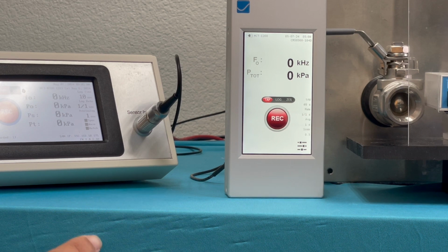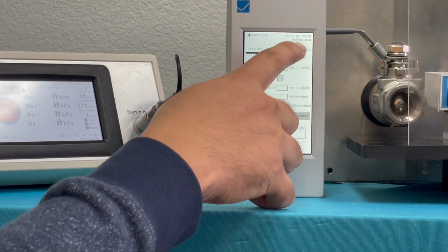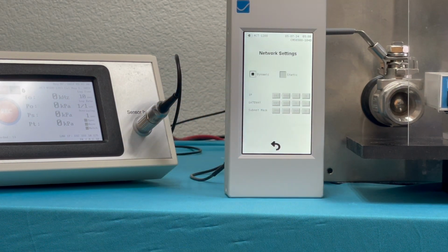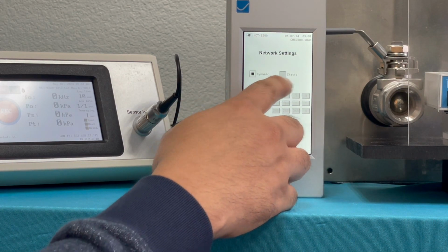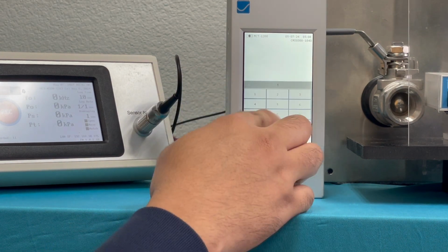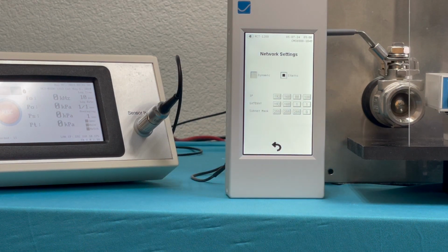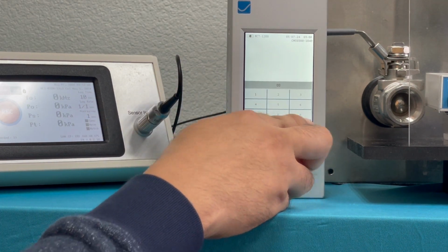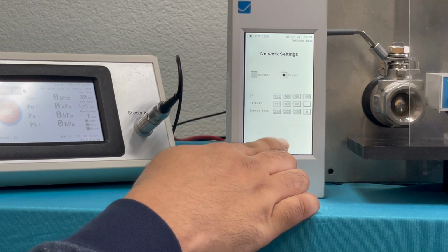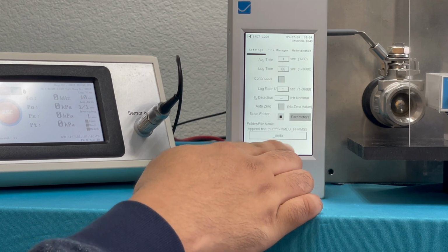First, we'll manually enter a static IP address. Just tap the menu icon to open up the menu options. Then head to Maintenance and select Set Network. Here, choose Static IP and start entering the IP address assigned to your PLC. Once you're done, hit the back icon, and like magic, your settings will save automatically to the MCT-1200, and you're all set to connect your unit to the network.